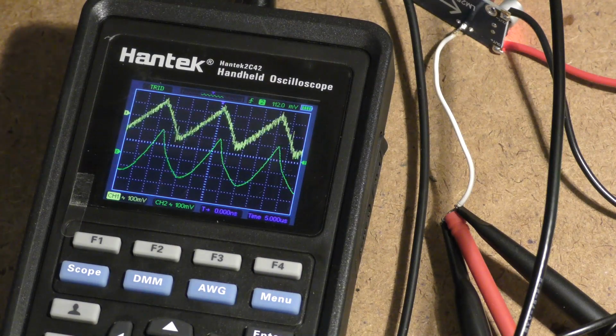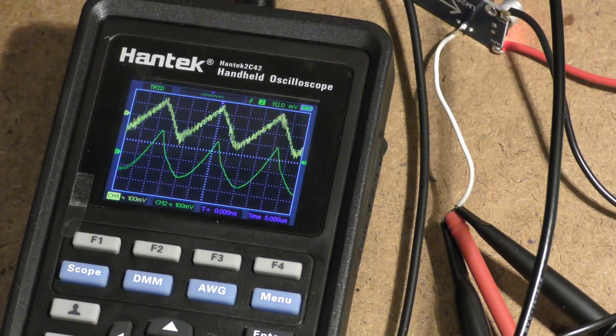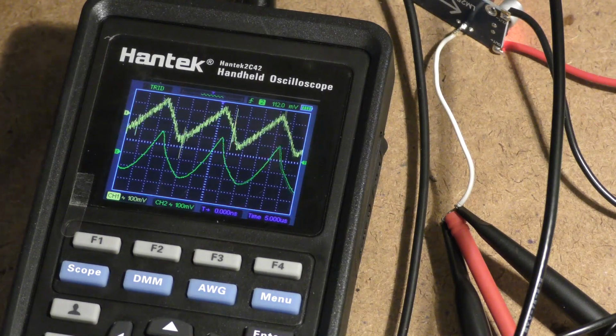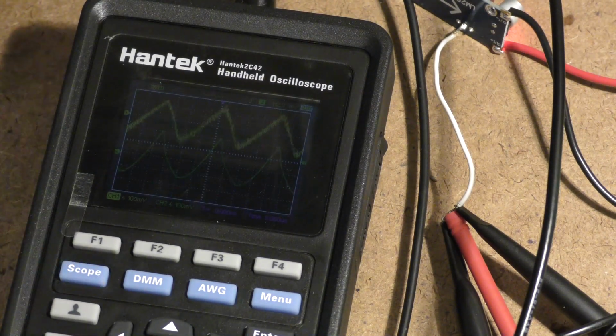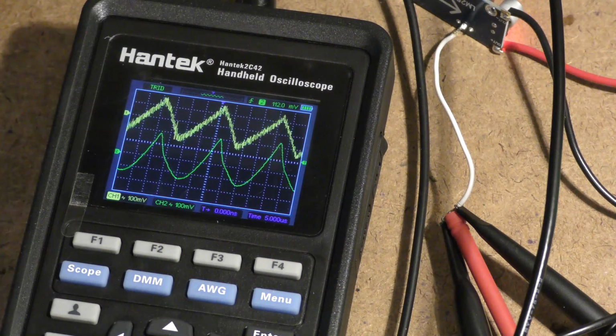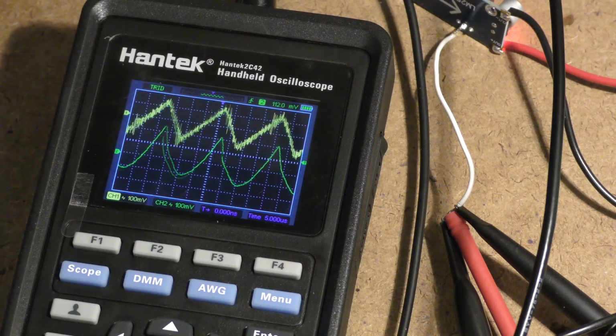And I bought this to replace a handheld oscilloscope that I've had for a very, very long time. The reason I bought it is I find handheld oscilloscopes to be especially helpful when you need the floating ground. In other words, when you're trying to measure a signal where the reference is not tied to the earth ground, the so-called green wire in your electrical system. Almost all lab oscilloscopes, or desktop or whatever you want to call them, have the negative of their BNC inputs all tied to the ground or to the green wire.